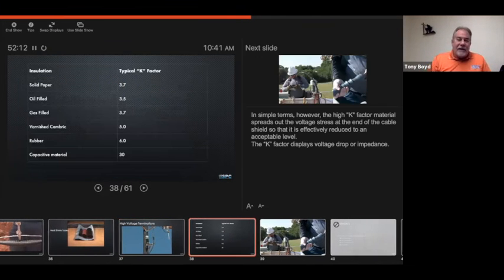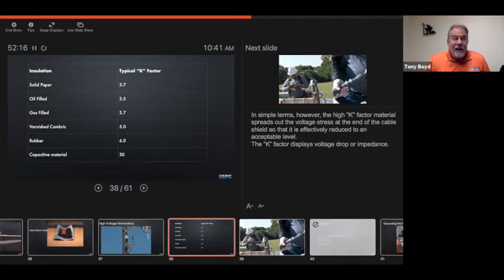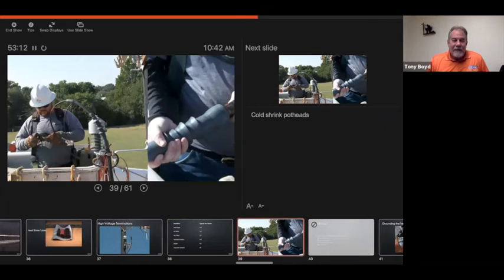All right, talk a little bit about insulation and a typical K factor of insulation. I mentioned early on we have paper insulated lead sheath cables. So solid paper gives a 3.7 K factor, which is just a type of measurement for your insulation on your cables. There's an oil filled, and most of your solid paper is an oil filled type paper, 3.5. There's a gas filled. Very expensive cables. I don't know of any that are left in use today. It was so expensive to splice, most of them just got replaced. Varnished cambric, I have no idea what that is. I have never heard of varnished cambric. And then the rubber, so your cross-linked polyethylene is right in there with the rubber at 6.0, and then a capacitive material. So the semiconductor material that we're talking about.